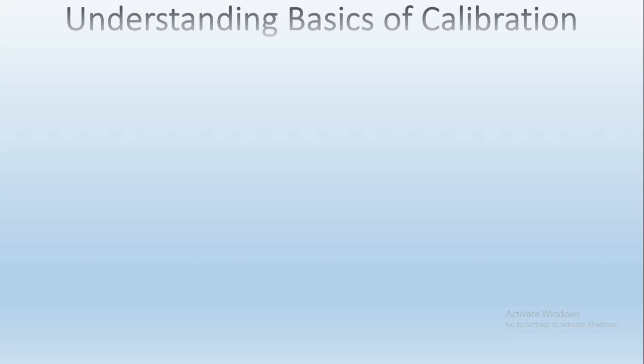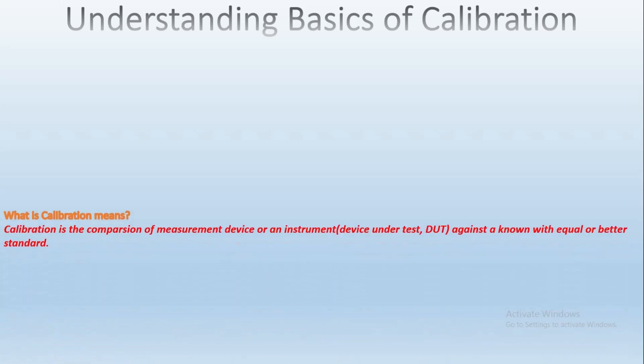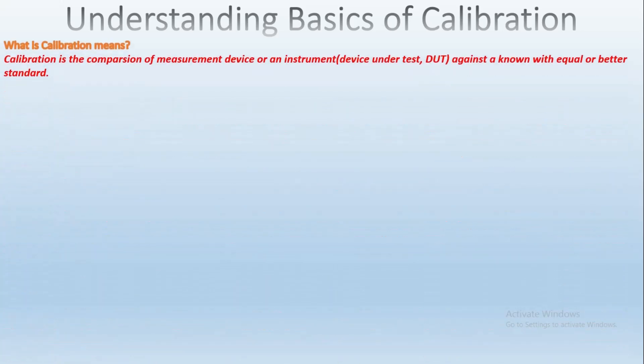Now we will know what calibration means. Calibration is the comparison of a measurement device or an instrument — that is the device under test, we will call it as DUT — against a known standard with equal or better accuracy. The standard in a measurement is considered to be more correct of the two.